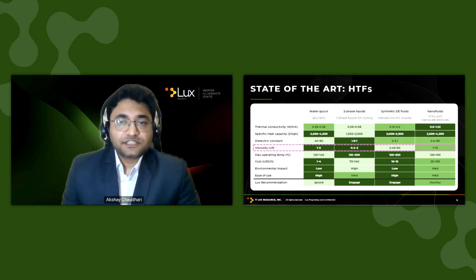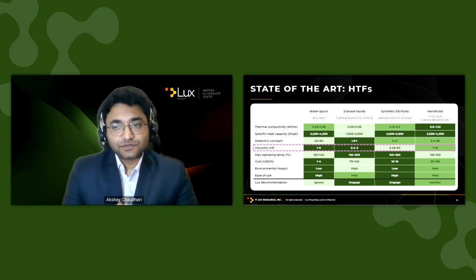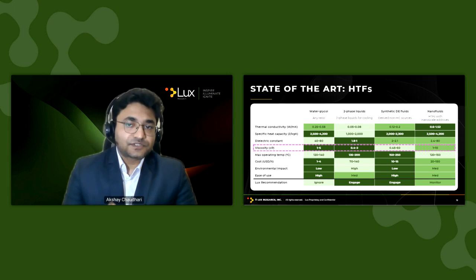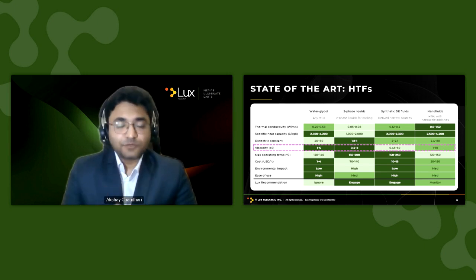For viscosity, water glycol and two-phase liquids are well suited due to their low viscosities. Whereas synthetic dielectric fluids have a very wide range, making only a few formulations suitable for this application.